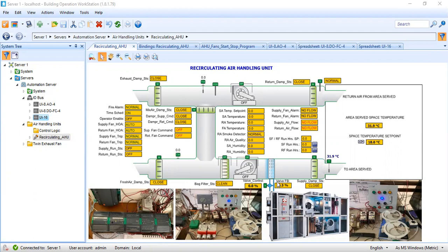Okay, because basically as a mechanical engineering practice, we are installing the valve at the return line of the chilled water system, or the chilled water piping. Now, as you can see, this is the valve. This is actually a three-way valve, okay, because we have three ports. So in, out, and the bypass. Now here, this is the valve of the coil.